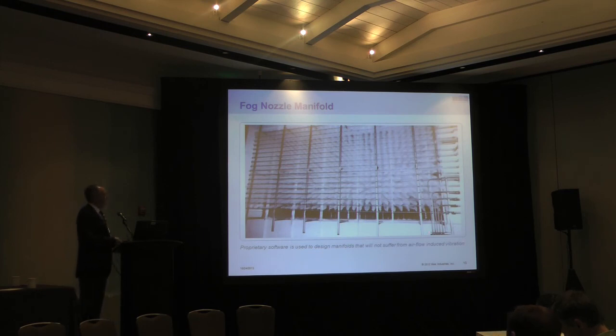These are high-pressure feed lines coming from, in this case, distinct high-pressure pumps. So there's 6 high-pressure pumps on the ground below the turbine inlet. These are high-pressure lines coming up. So one of these feed lines will feed multiple nozzle lines, and we try to spread them out. So the first stage might be one on the top and one on the bottom and one in the middle and another one in the middle. So they're kind of overlapping staging. That's to avoid uneven cooling at the compressor inlet.